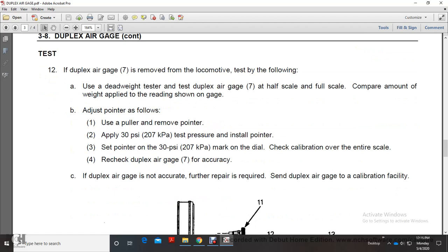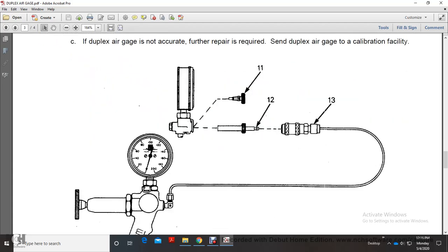Set the pointer on the 30 PSI marking on the dial. Check calibration over the entire scale and recheck the duplex air gauge for accuracy. If not accurate, further repair is required. Send the duplex air gauge to a calibration facility.